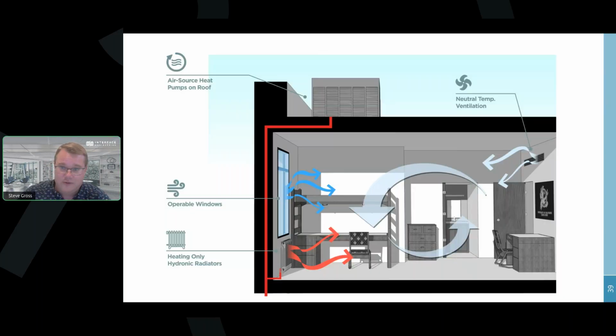This is where we started the project: a pretty typical, mild-climate system providing heating only, along with mechanical ventilation delivered near neutral temperature—close to the indoor air temperature. In heating season we deliver air at 70 or 72, and in cooling season at 75 or 76 degrees. This is typical, to limit the energy consumption associated with ventilation and limit the size of the dedicated outside air system equipment.